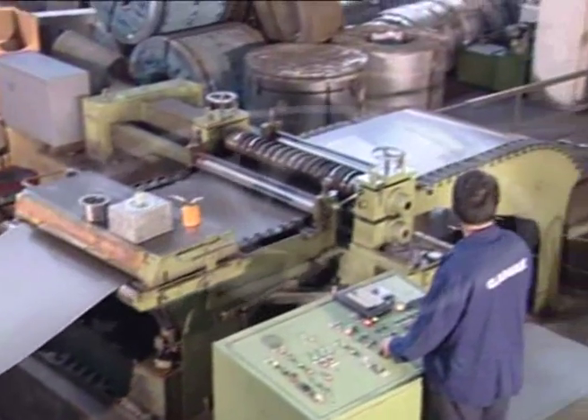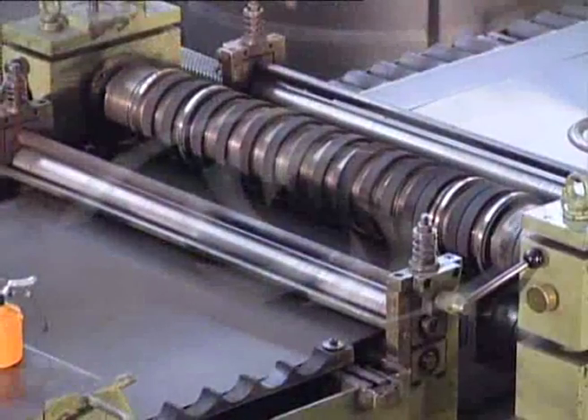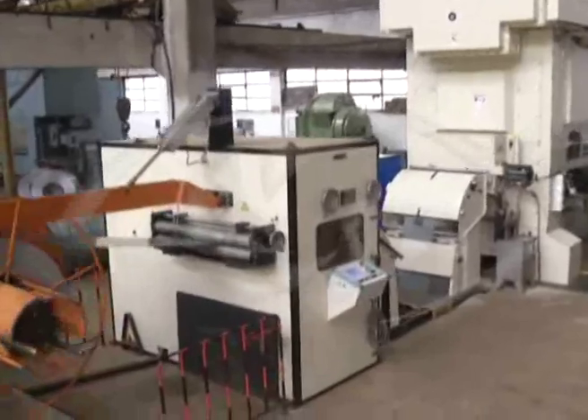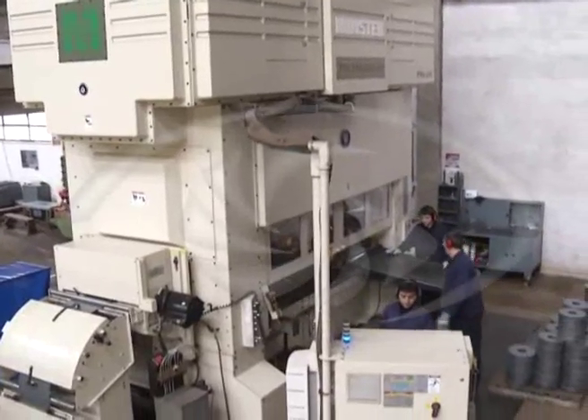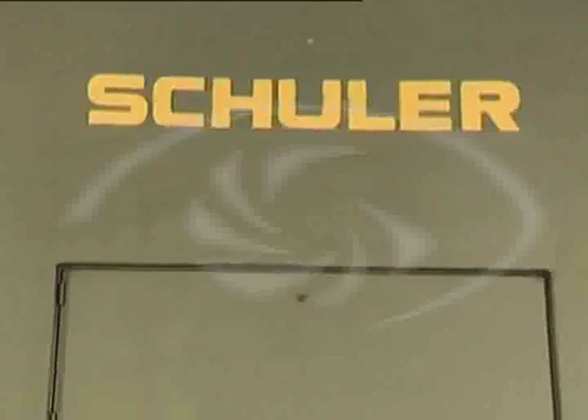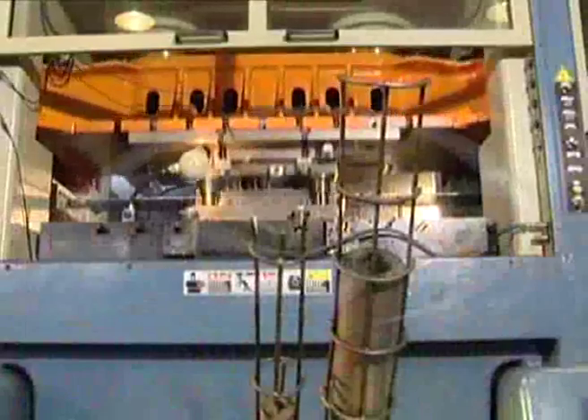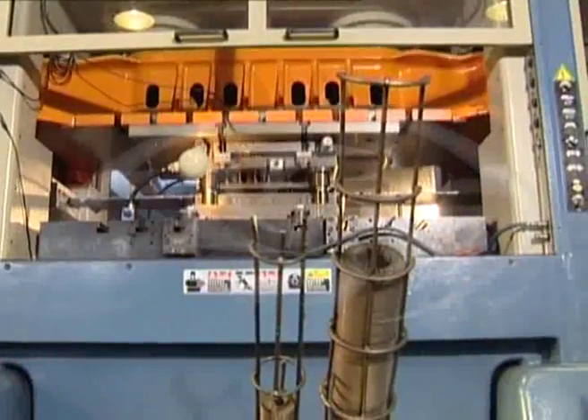The raw material coils of high-quality silicon steel are taken to the first fabrication step for slitting. Coils of 1000 mm width are cut in different sizes for their use in stator and rotor laminations. The slitted coils are then taken to high-speed presses for punching with progressive type dies. Each of these presses have the capacity of punching up to 400 tons of force and speeds of 600 punches per minute.